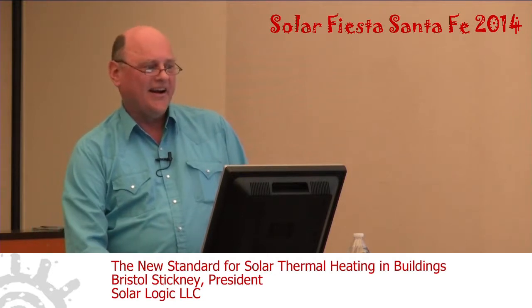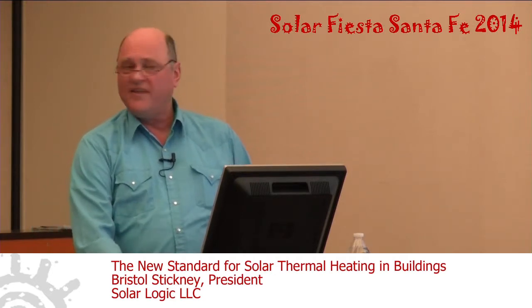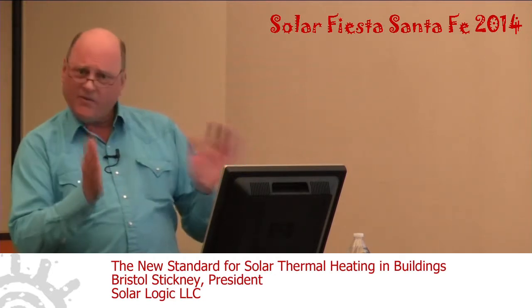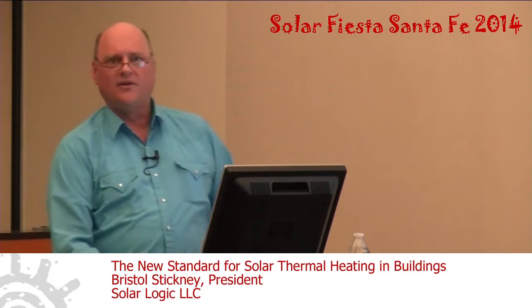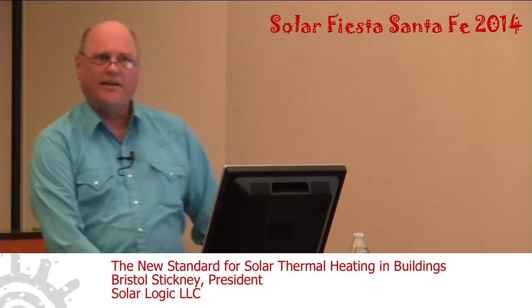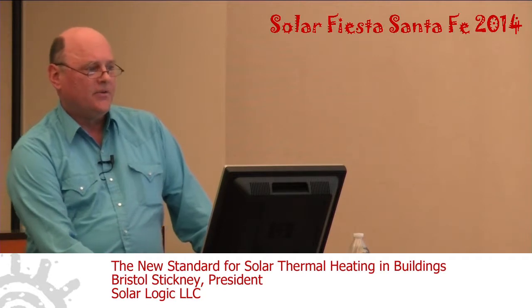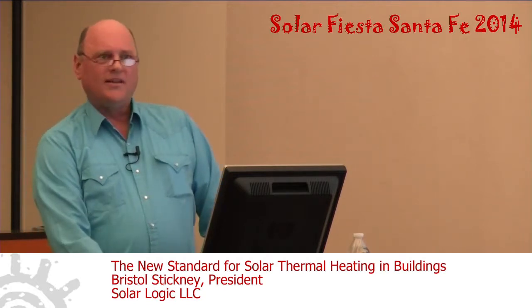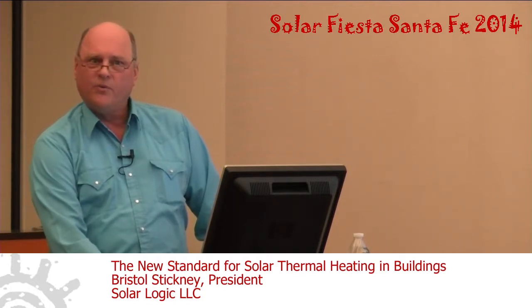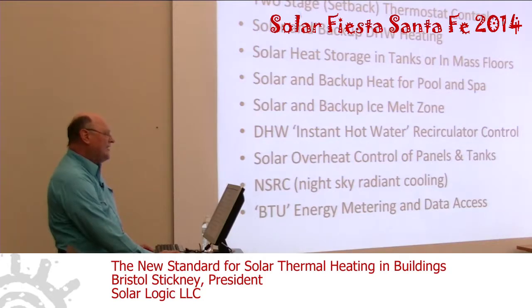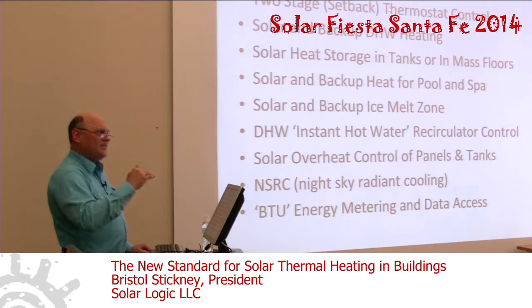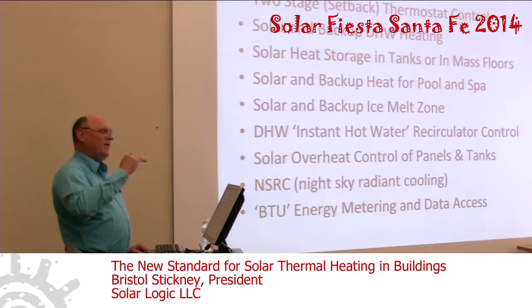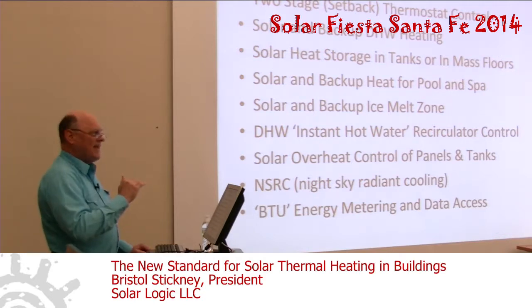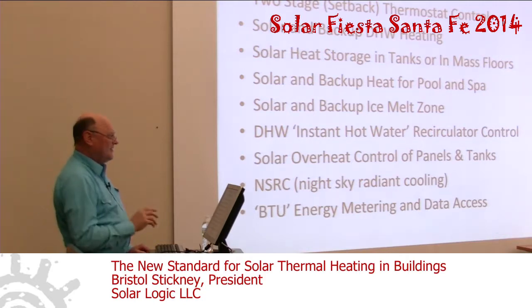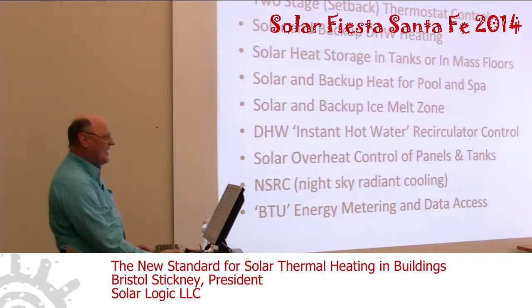And what you see here is quite a long list of things that really need to be watched over and controlled properly in order to make a solar heating system work well in a building. You really do need to know what the temperatures are in every room, and to control them in 2 stages. You want to let it get a little warmer when it's solar, but not so warm maybe when the boiler is kicking in. So that's called 2-stage thermostat control.